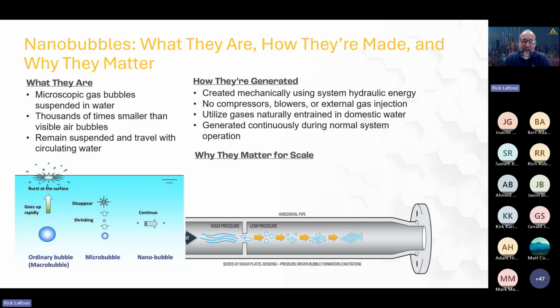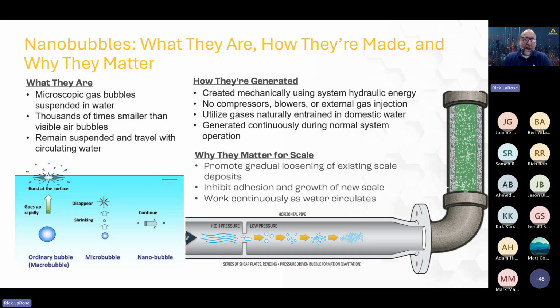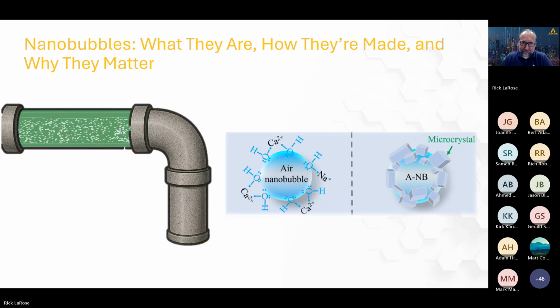The cool thing is that the bubbles remain present throughout the whole system, and they're microscopic, so they go everywhere, into every little nook and cranny, every little valve seat, everywhere they can, to both remove the scale and keep it from forming back in those places, precipitating out. Over time, this basically cleans the system and keeps the scale from coming back.